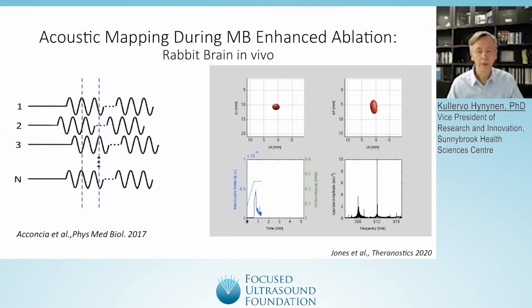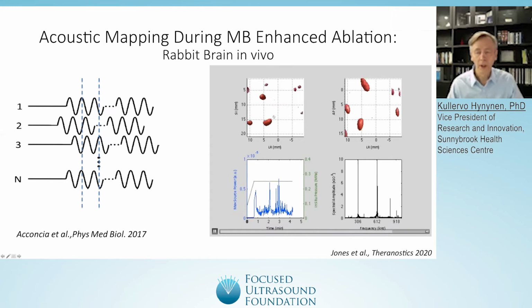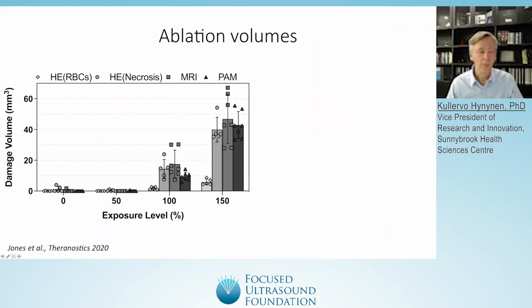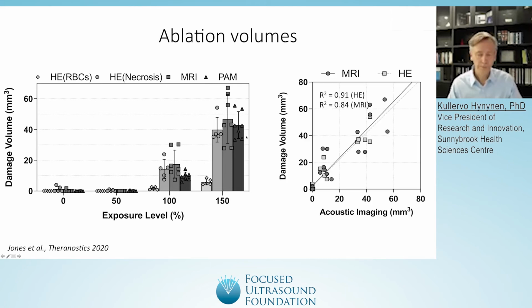And so we have this time information, and at each location we have the spectral information. Here you can see the subharmonic signal, and then we can form four-dimensional maps of the bubble activity. And from that, we can calculate the tissue damage. So here is now, from many animal experiments, the tissue volume that was damaged, and here is the exposure level. At the lower levels, we don't see any tissue damage. At the 100% level, we start seeing some tissue damage. At the 150% level, we have nice tissue damage, and you can notice that the histological tissue volume, the MR-derived tissue volume, and the passive acoustic map tissue volume are almost equal. So it looks like we can use the passive acoustic mapping to tell what tissue volume was damaged.